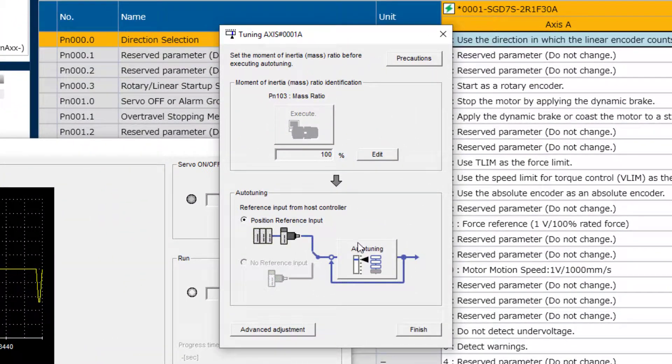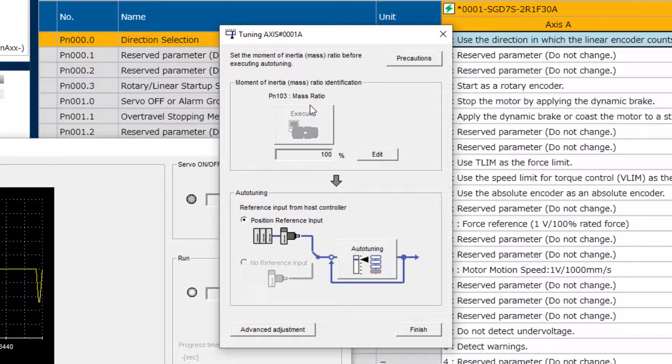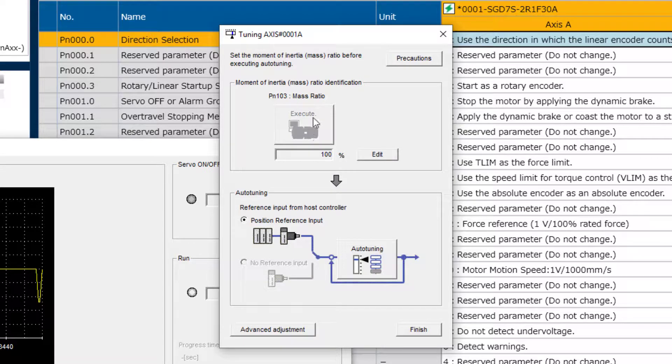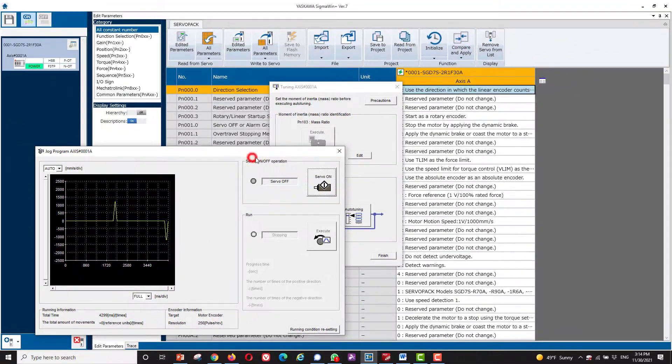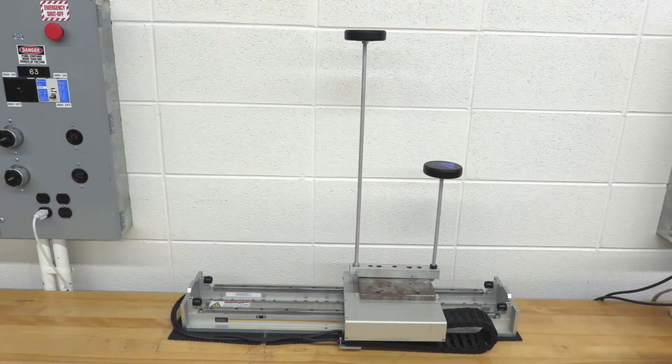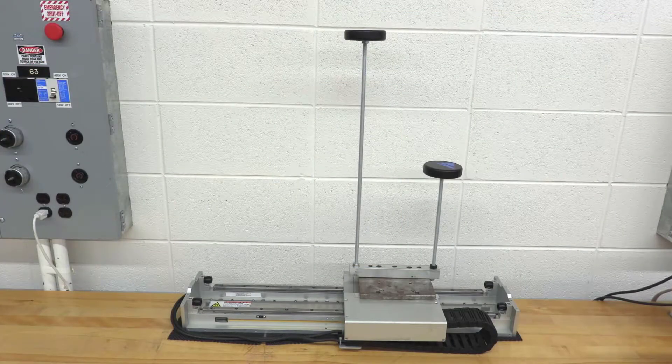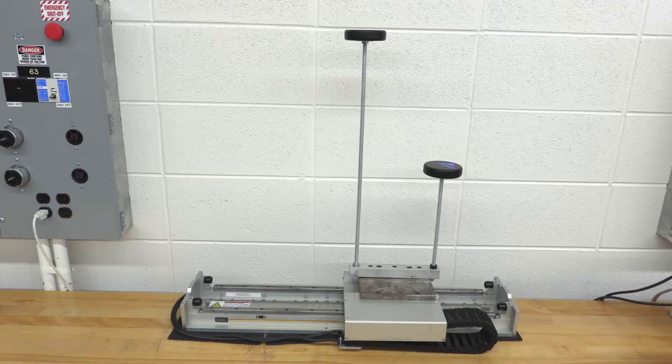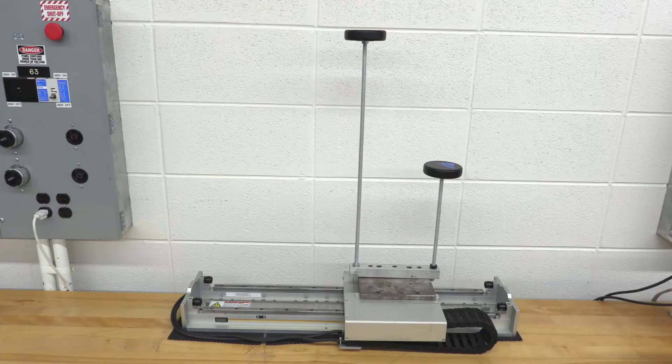But before you jump to auto-tuning, it's important to first find the inertia ratio, or in this case, mass ratio. If that's grayed out, then you just need to close any conflicting windows. And also, you want the machine somewhere in the middle of its range of motion since the motor is going to move in both directions when you find the mass ratio.